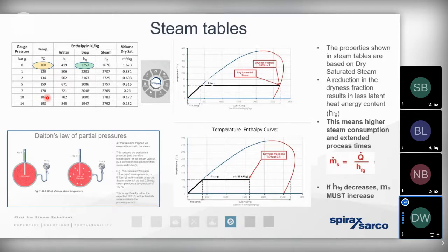But if we've reduced the pressure of the steam to control the temperature, let's say we've got a process, a heat exchanger, that only requires the steam to exist at 134 degrees. Well, we can achieve that by reducing the pressure down to 2 bar gauge. But at that point, the condensate will also exist as a liquid at 2 bar gauge at 132 degrees. So it'll exist as a liquid at that point because of the pressure.